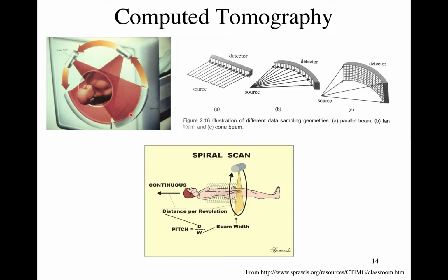The big jump in technology, Siemens did this first in the mid-'80s or so. Instead of having those cables, they put a set of contacts on a slip ring. Those contacts were like brushes sitting on the side, and then they could just keep rotating the thing, and all of the signal came out on these brushes on the slip ring. So you could rotate in one dimension, just keep it rotating.